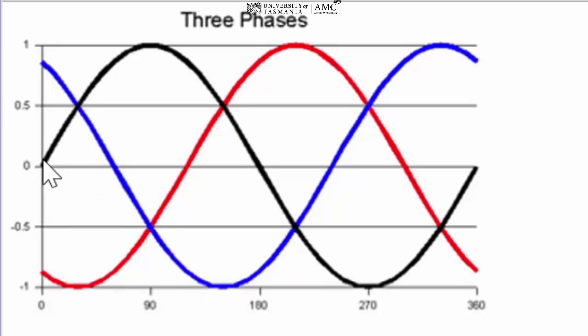And to do that, the black phase on the incoming has to start at exactly the same point. If they're any little bit out of phase, then it's going to do destruction to the switchboard or some of the gear, perhaps even the alternator. So the black phase has to come in at exactly this point, the blue phase has to come in at exactly this point, and the red phase. All three of the phases have to be synchronized at the same time.